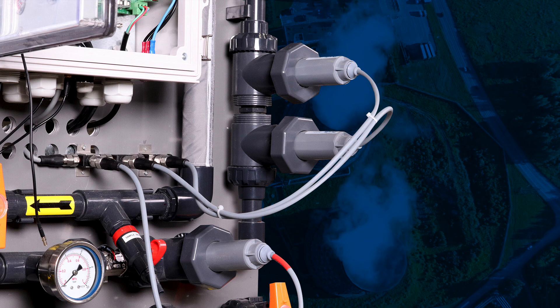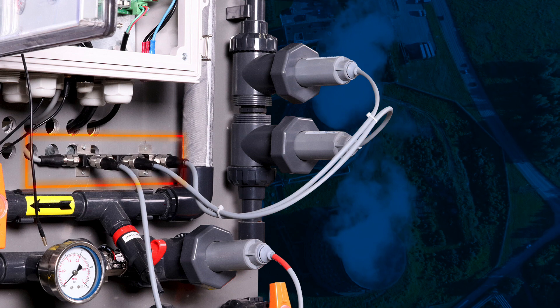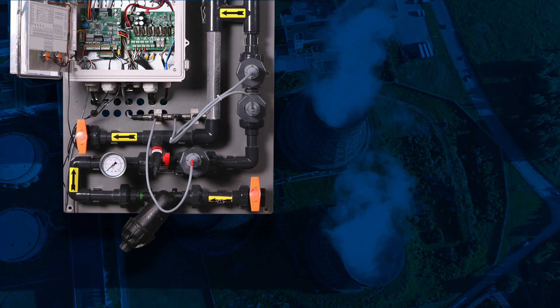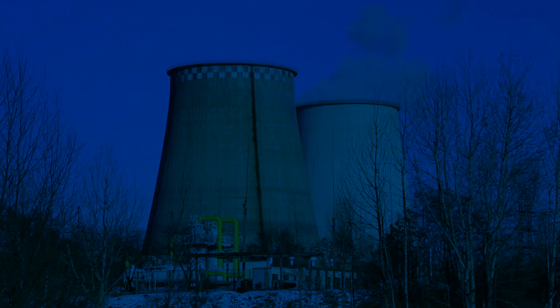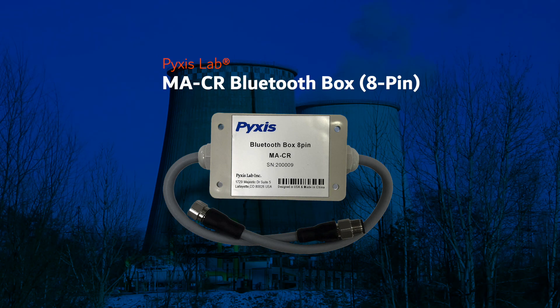This unique configuration allows an unlimited number of Pixis 5-pin sensors to be interconnected using the RS-485 Junction-T provided with the sensor, eliminating the need for each sensor to be wired independently. In a 5-pin format, users may integrate an MACR Bluetooth adapter as part of the multi-drop array prior to the controller, allowing for wireless access via the uPyxis app to all Pyxis sensors connected in that array.